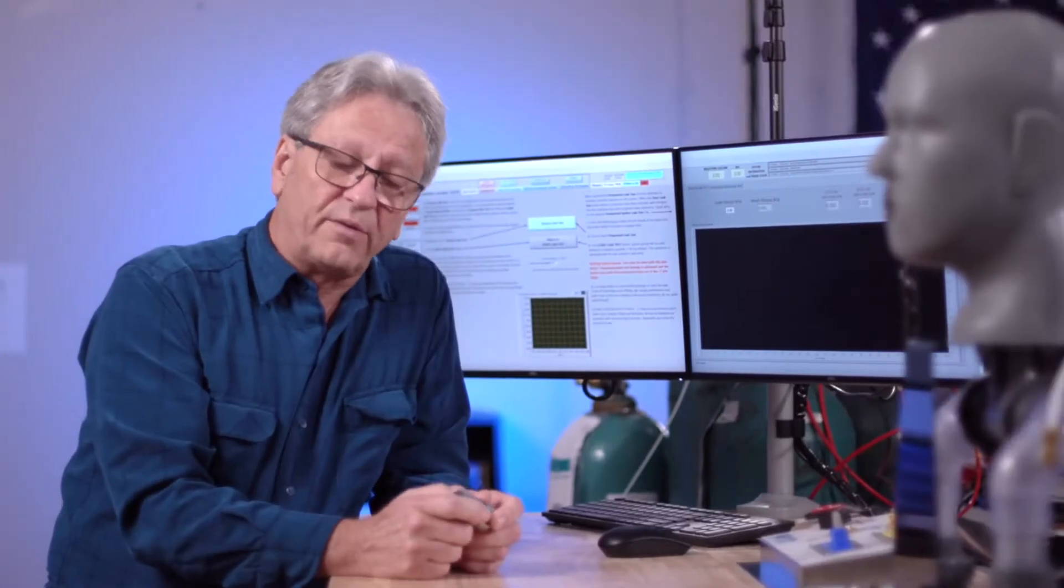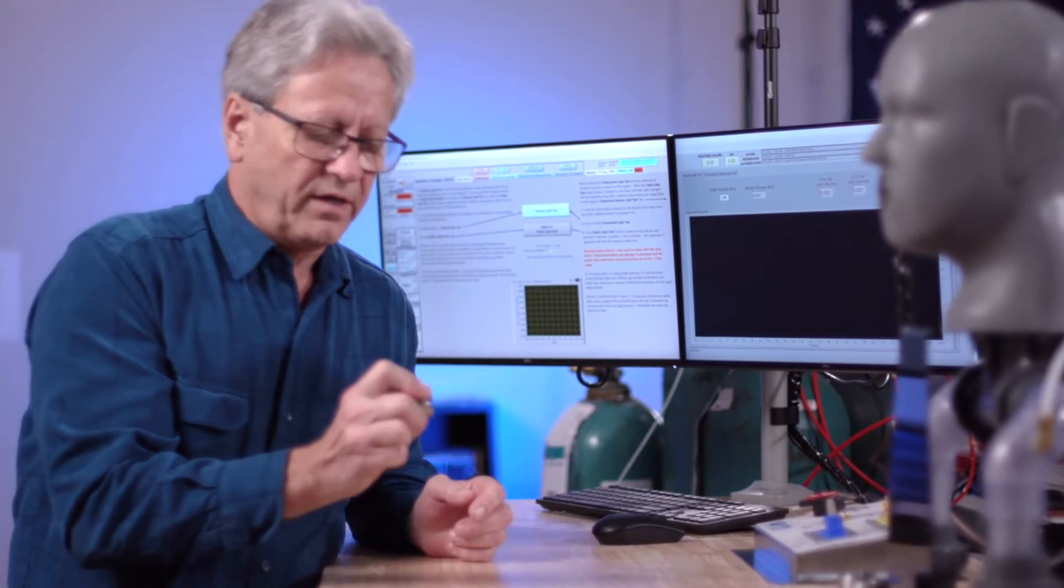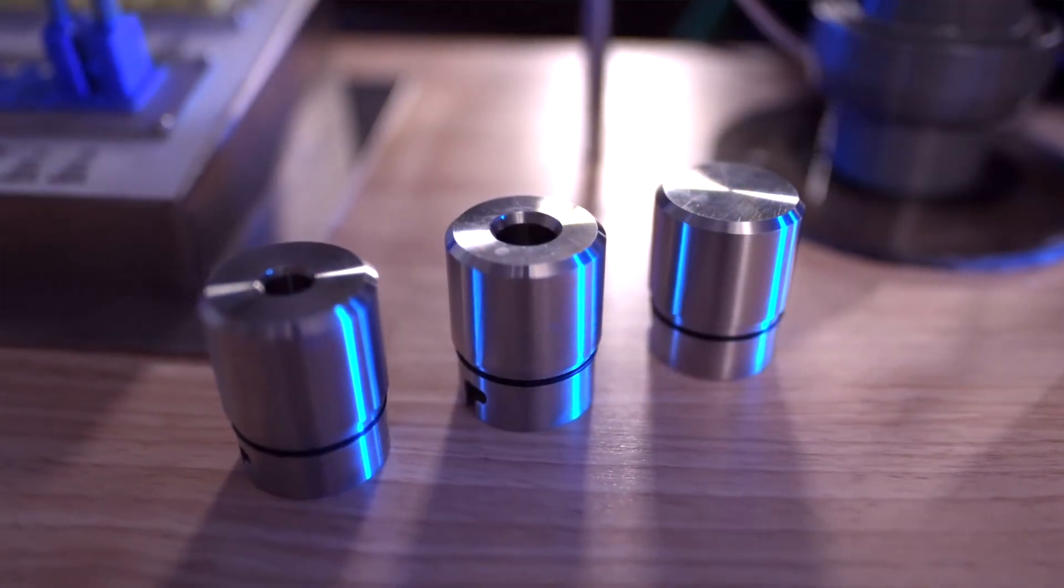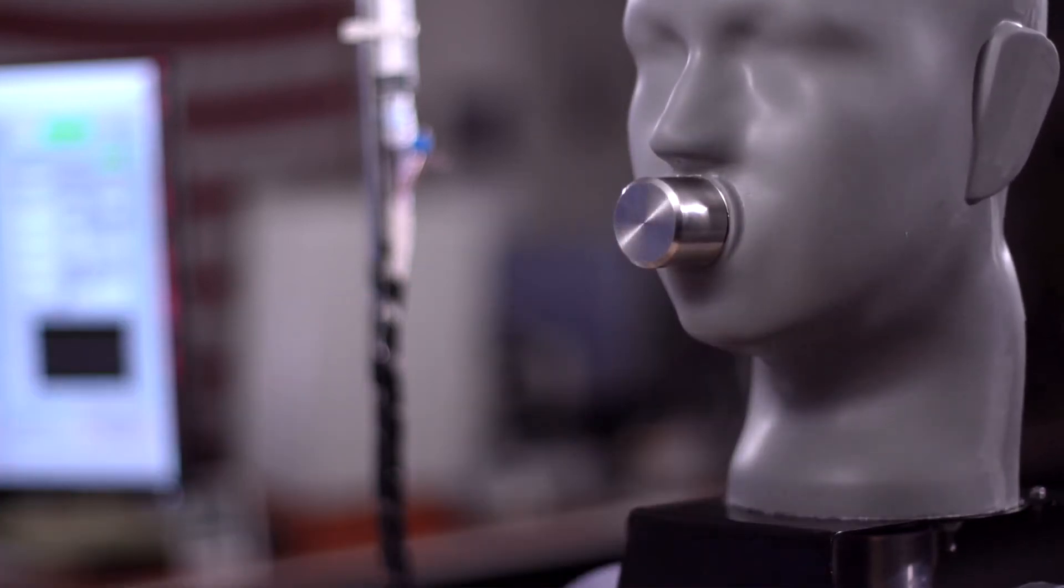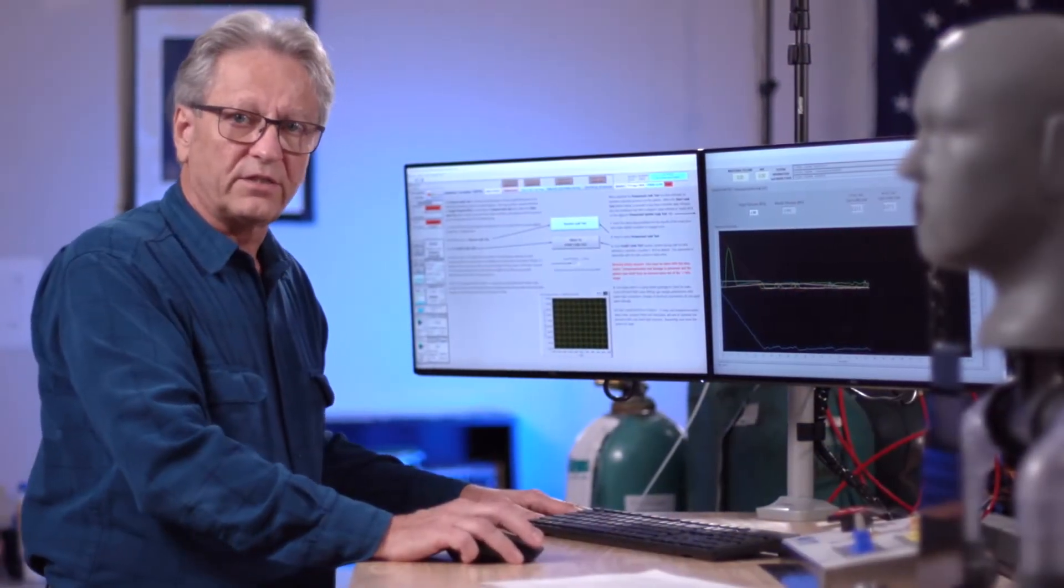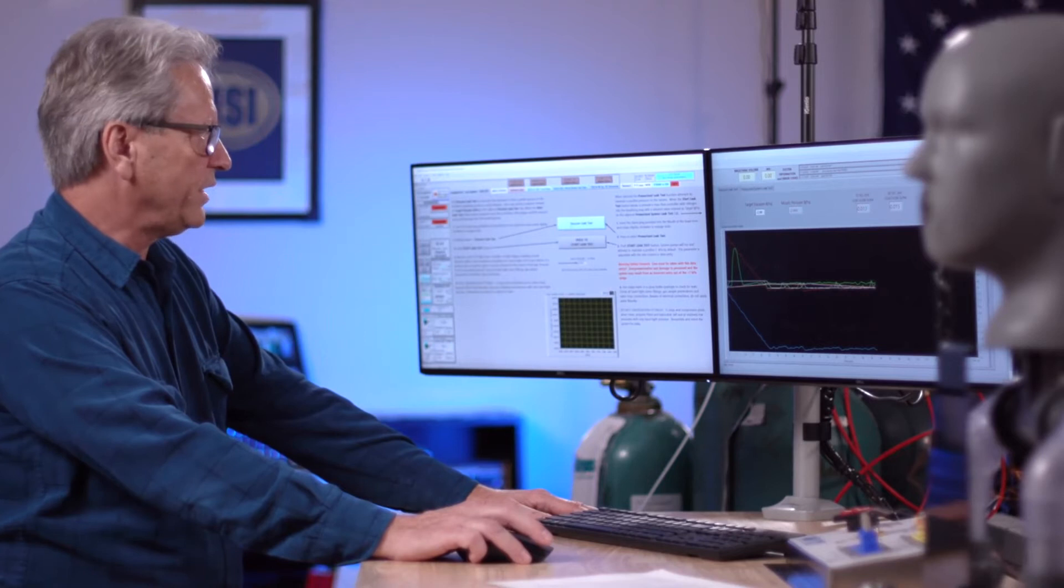In this video segment, we're going to evaluate the inwards leakage rate of our system. Here we have a mouth plug that I can insert and our system will draw a vacuum in order to evaluate the integrity of the breathing system. The ABMS has two separate leak test procedures. One is a vacuum leak test and the other is a pressurized leak test.